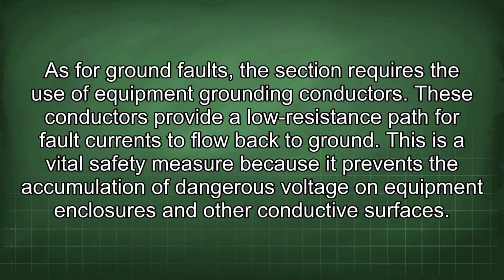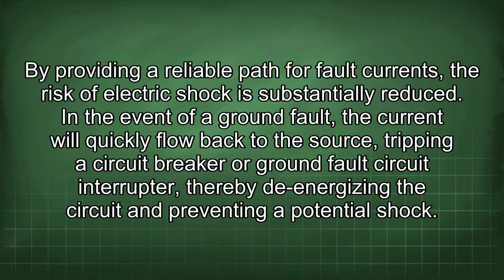As for ground faults, the section requires the use of equipment grounding conductors. These conductors provide a low-resistance path for fault currents to flow back to ground. This is a vital safety measure because it prevents the accumulation of dangerous voltage on equipment enclosures and other conductive surfaces. By providing a reliable path for fault currents, the risk of electric shock is substantially reduced. In the event of a ground fault, the current will quickly flow back to the source, tripping a circuit breaker or ground fault circuit interrupter, thereby de-energizing the circuit and preventing a potential shock.